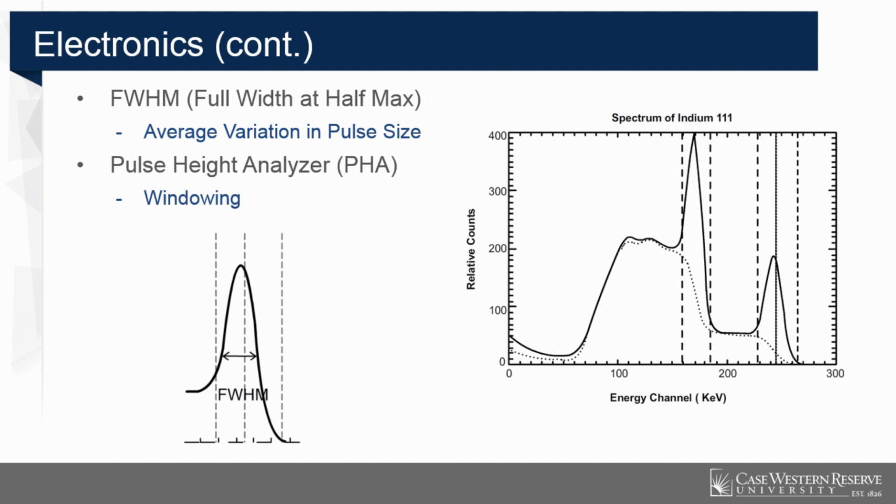But going through the body, because of Compton scattering, you ended up with those shoulders. The dotted line shows the photons that are scattered either once, twice, like the lower shoulder. These are 3 times, 4 times, maybe 5 times. We do not want those scattered photons in the image because they represent wrong information. They will decrease the spatial resolution, image sharpness.